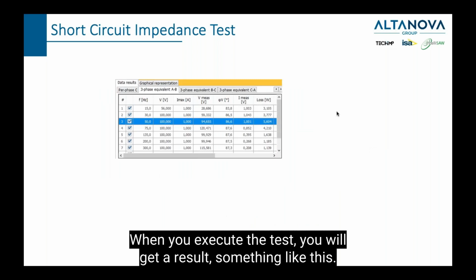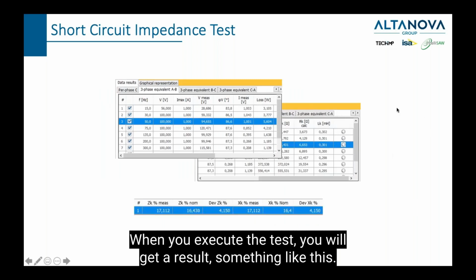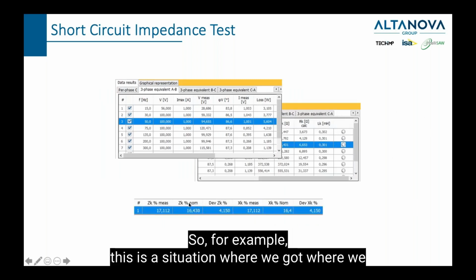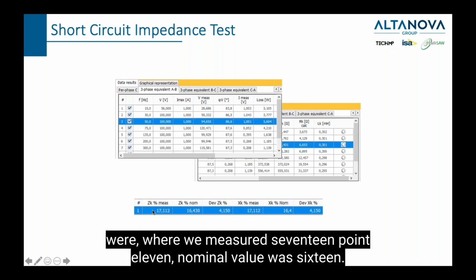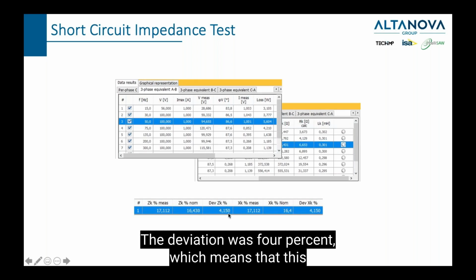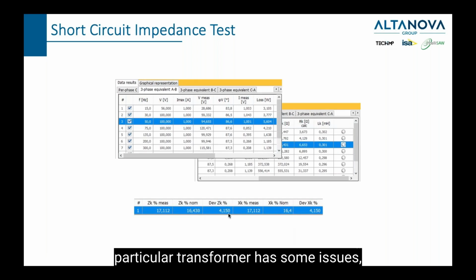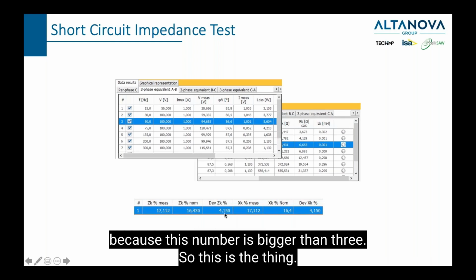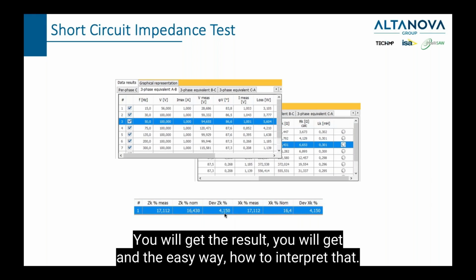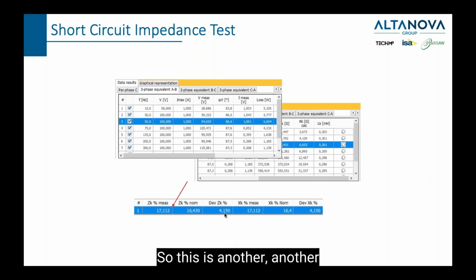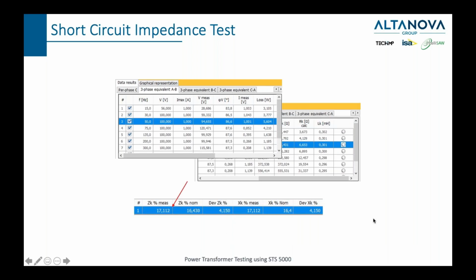When you execute a test, you will get a result, something like this. For example, this is a situation where we measured 17.11, the nominal value was 16, and the deviation was 4%, which means that this particular transformer has some issues because this number is bigger than 3. So this is the result you will get, and the easy way to interpret that. So this is another example.